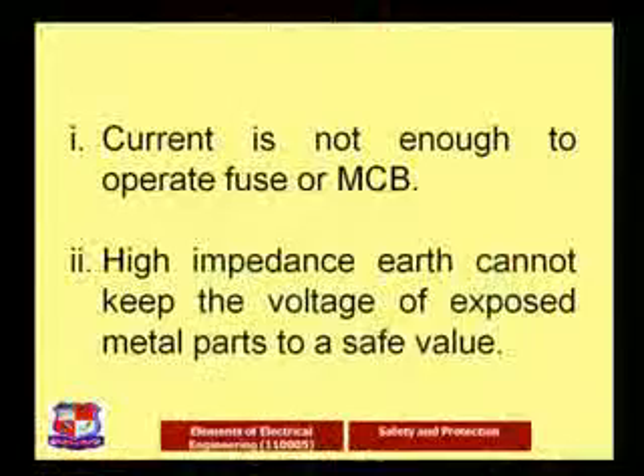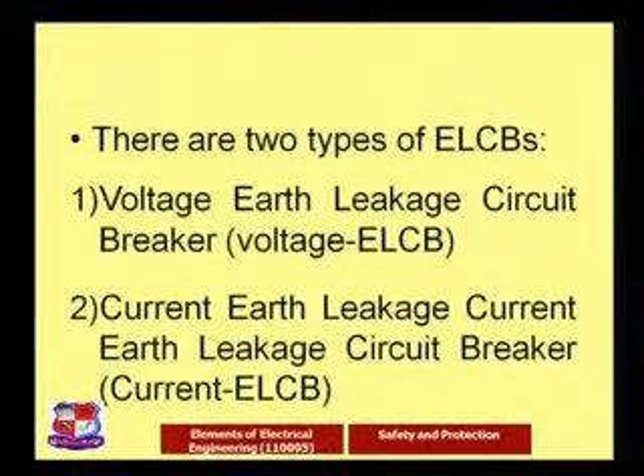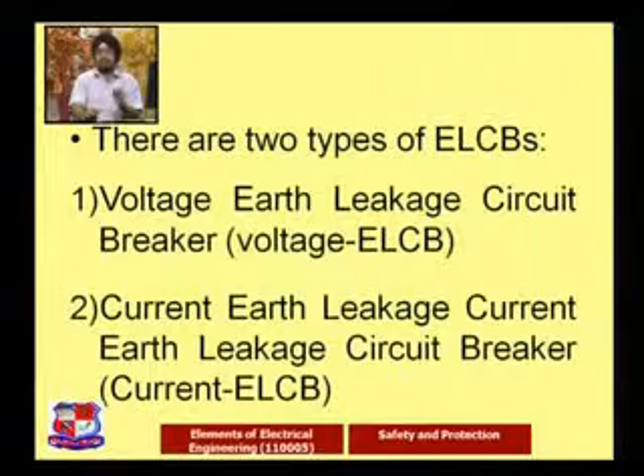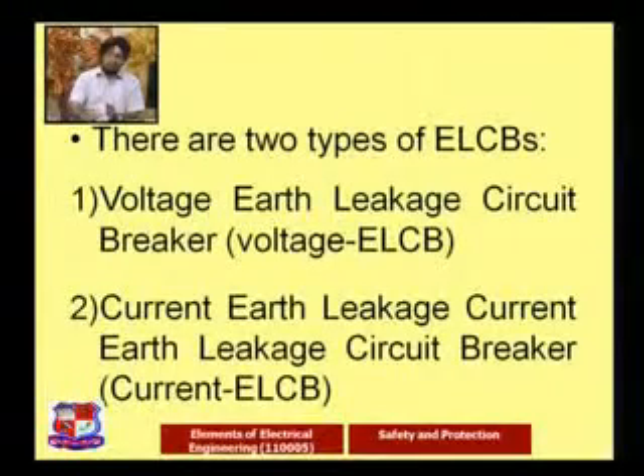So when current is not detected properly going to the earth, or the magnitude of the current is not there, and at the same time the impedance of the earth cannot keep the voltage off the exposed part, in that case the ELCB is very important. Now there are two types of ELCBs, as we discussed. One is with respect to current, one is with respect to the body voltage. One is connected in series, one is the shunt one. The shunt one means voltage plays the role, and that ELCB is known as the voltage ELCB, meaning voltage earth leakage circuit breaker. The second one is the current earth leakage circuit breaker.